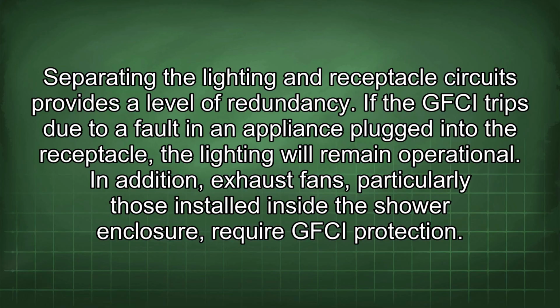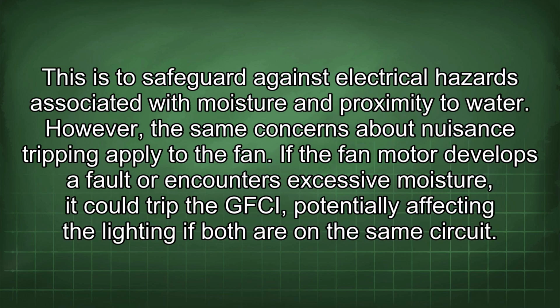In addition, exhaust fans, particularly those installed inside the shower enclosure, require GFCI protection. This is to safeguard against electrical hazards associated with moisture and proximity to water. However, the same concerns about nuisance tripping apply to the fan. If the fan motor develops a fault or encounters excessive moisture, it could trip the GFCI, potentially affecting the lighting if both are on the same circuit.